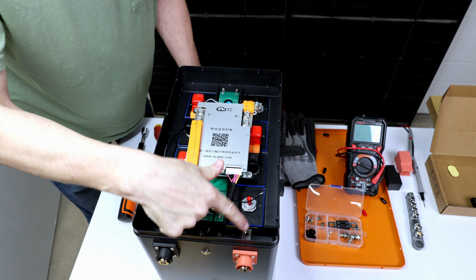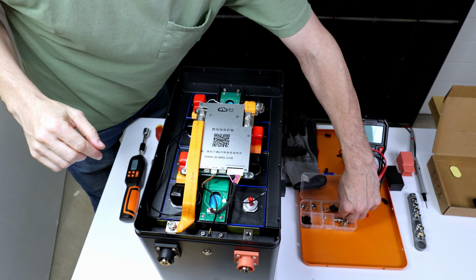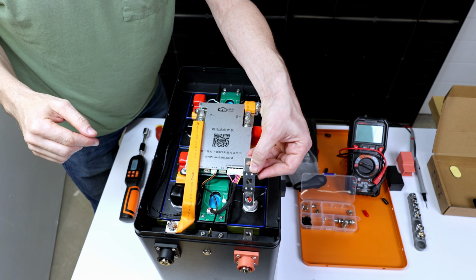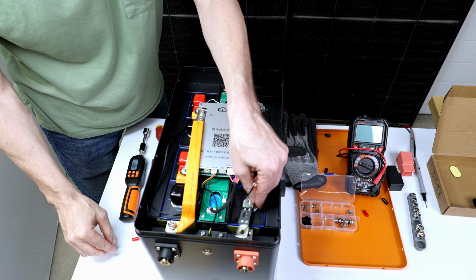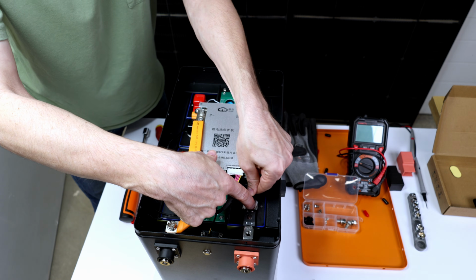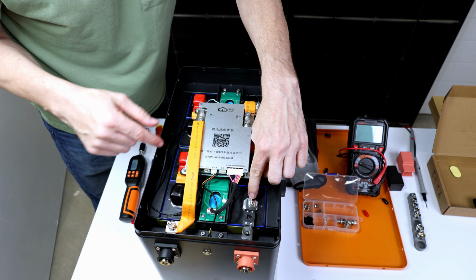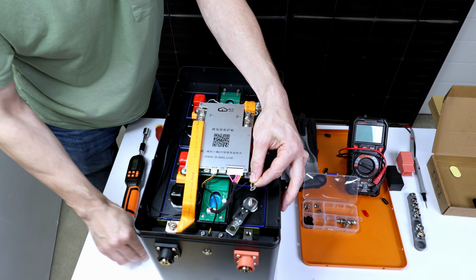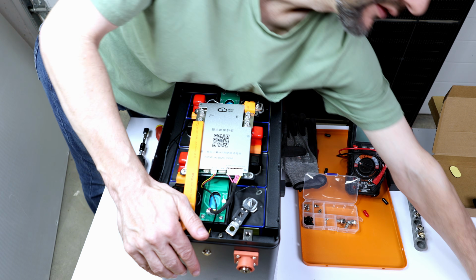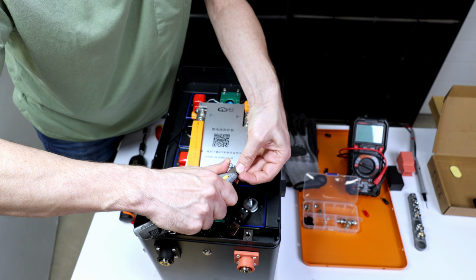All right, now this final connection is actually made with this 250 amp fuse, so we'll drop that on there. Our final voltage sensor goes in with that. Make sure that the nut doesn't pinch any of that insulation. And it is going to touch it, so trim just a little bit of that.